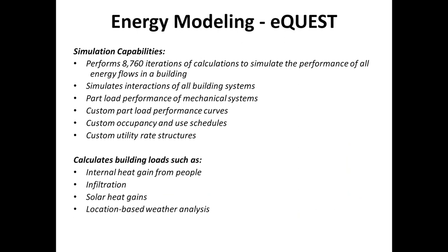It accounts for interactions between building systems, so it accounts for the lighting load in the building and how that affects the cooling system, the heating system, the ventilation. You can import and customize part load performance curves. So you can call out specific fans and change the fan curves. You can change the performance curves of a boiler or a chiller, and get extremely detailed to see how the different measures affect a building. It also calculates things such as solar heat gains based on the location. It looks at the typical weather data for the typical year: solar heat gains, infiltration, and also the scheduling, how many people go into the building and the internal heat gain attributed to those people.